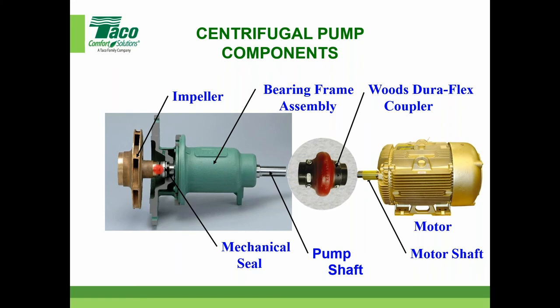John Crane Type 21 is pretty standard. There are some options out there for different materials. Keep in mind, these are mostly clean water pumps. Right? I don't need to give you the definition of clean water, but nonetheless, it doesn't have a lot of chemical capabilities. But one thing it doesn't like is grit and sand and any type of dirt or anything like that. That really will be the first thing to destroy a mechanical seal.